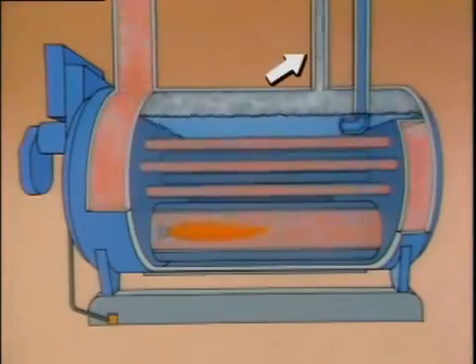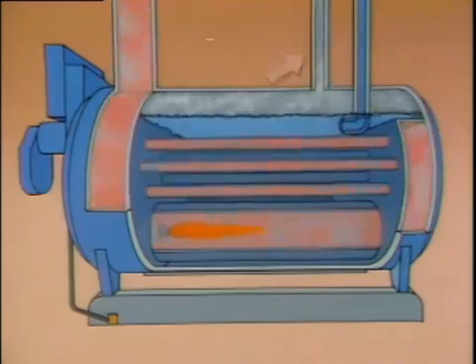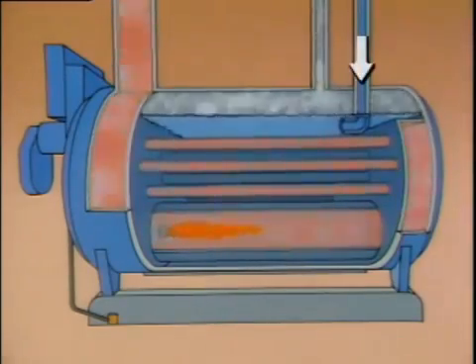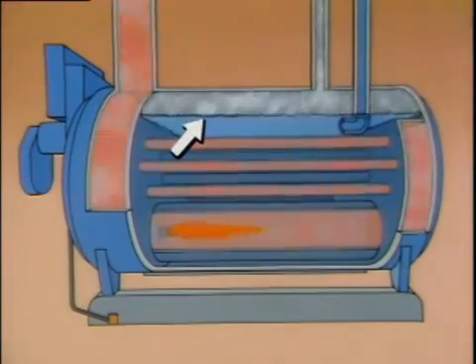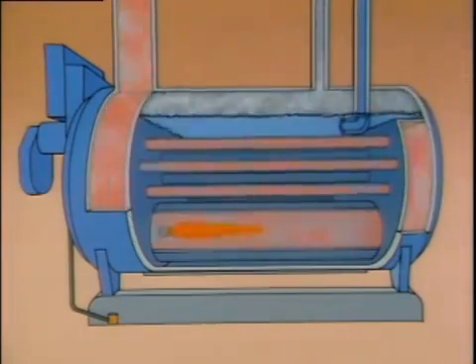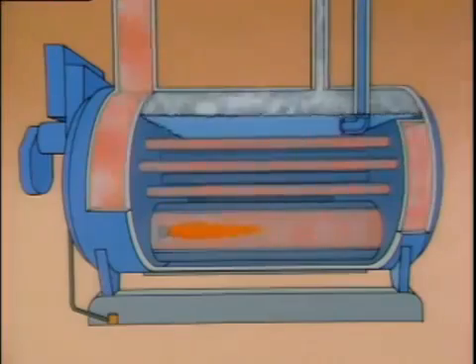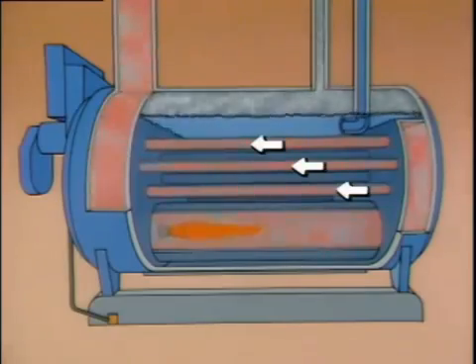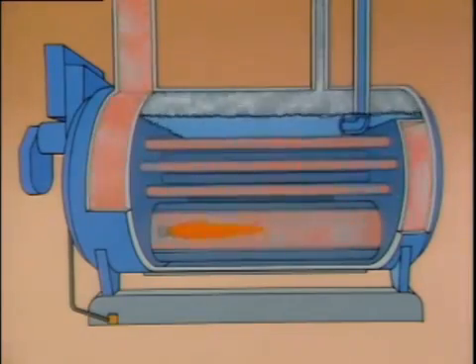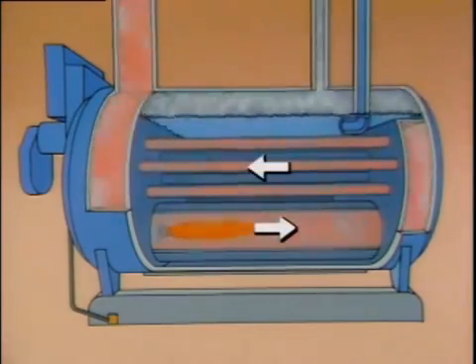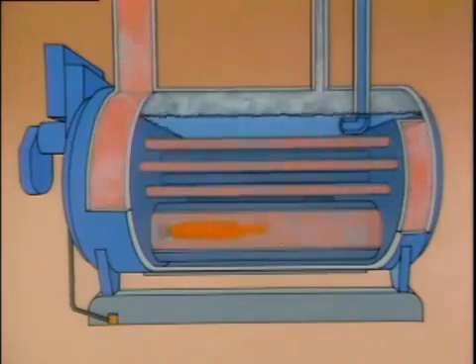There's also an outlet for the gases, a feed water line, and a steam outlet line. During operation, water enters through the feed water line. The water level is maintained above the fire tubes to protect the tubes from overheating. Fuel and air enter the combustion area. The burning fuel transfers heat to the water in the shell. The hot gases flow through the fire tubes, and additional heat is transferred to the water surrounding them. Each time the gases are routed through the shell, it's called a pass. The gases pass through two times in this example, so it's a two-pass boiler.